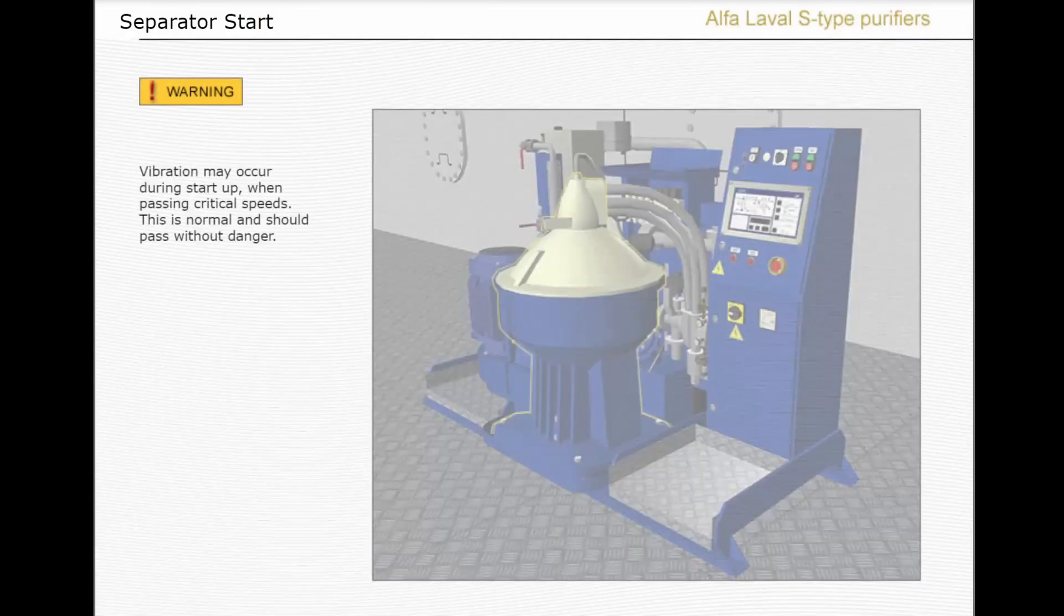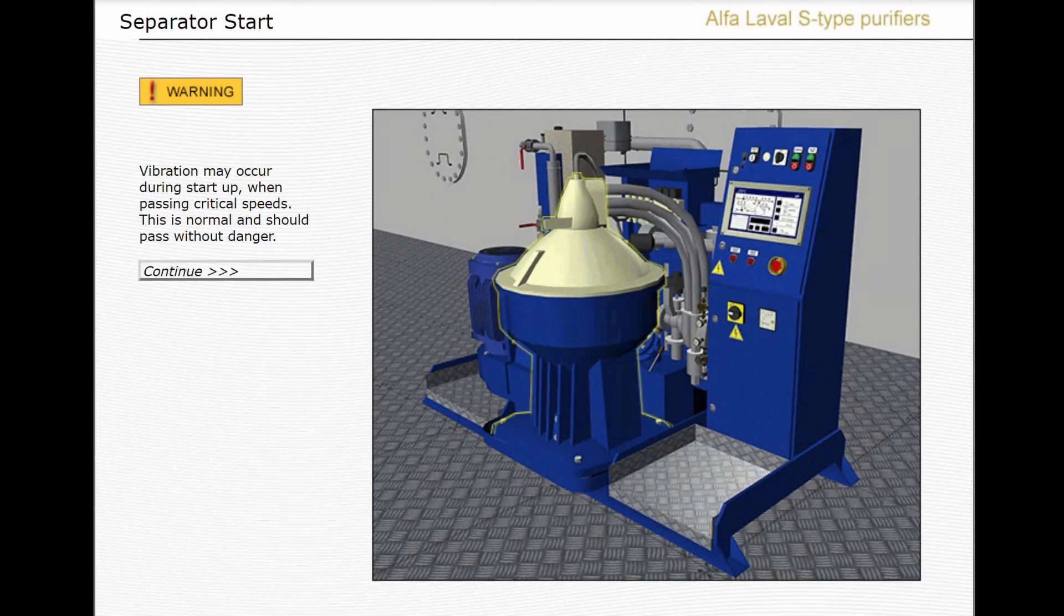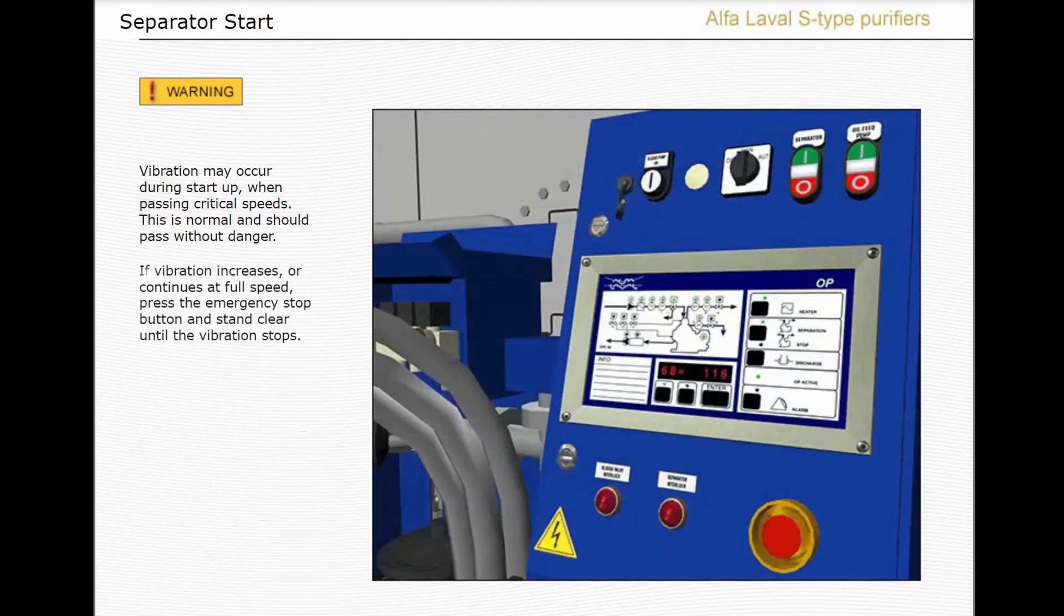Listen and observe the start-up process. Vibration may occur during start-up when passing critical speeds. This is normal and should pass without danger. If vibration increases or continues at full speed, press the emergency stop button and stand clear until the vibration stops.